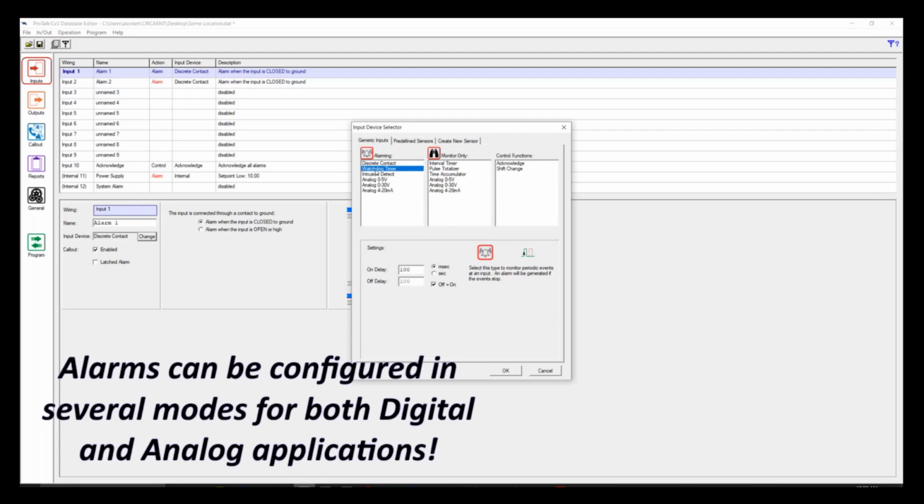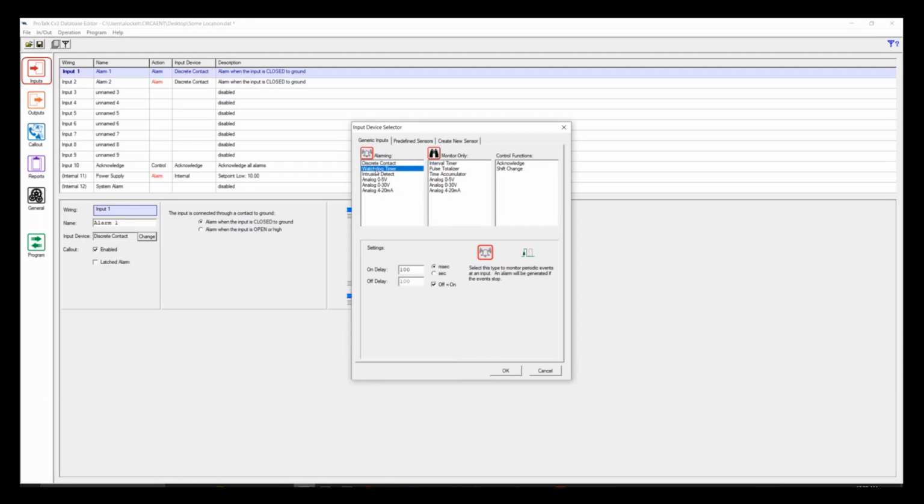Only the last four alarms can be programmed with the analog 4-20 mA input type. Within the analog type, you can set a delay if the value will be constantly changing, and you want to know if it's too high or too low. Here you will also set your measurement values for what 0 and 100 means. Hysteresis denotes the tolerance for either side of the range, basically the resolution.